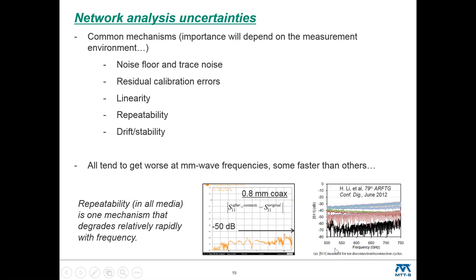But over on the right is a waveguide measurement. Now this is higher frequency, about a factor of 5 higher. Same kind of concept where we just disconnect and reconnect, but this was only 6 times. You'll notice, and it's the same metric, but the numbers are creeping up into the 20s. That's pretty significant, and that's going to swamp all these other uncertainty terms. Now this is with a classic waveguide flange, which was designed many years ago with dimensional tolerances that were more appropriate for lower frequencies. So in recent years, there have been new standard flanges developed - P1785 is the name of one such standard to help improve those repeatability numbers.